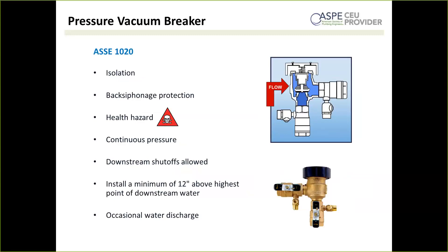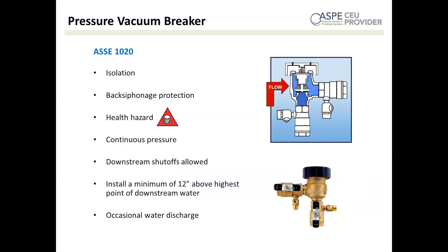Our first true testable backflow preventer is a pressure vacuum breaker. Like an atmospheric vacuum breaker, these are for back siphonage only, are appropriate for health hazard applications, must be installed above the highest outlet point — in this case 12 inches above — and can occasionally discharge water. The big difference is they can handle continuous pressure, so you can have shutoffs downstream. They're allowed continuous pressure because they have a spring that forces the float vent down at low pressure, avoiding the stuck-float risk of an atmospheric vacuum breaker. They also have a single check valve for added protection and are most commonly found on residential sprinkler systems.